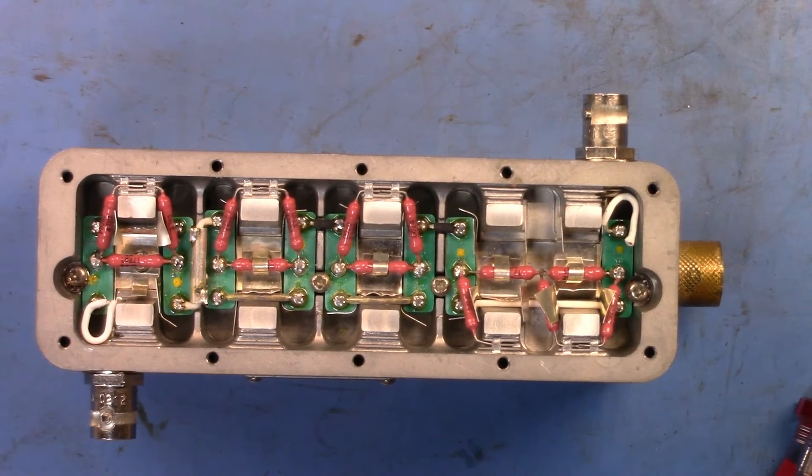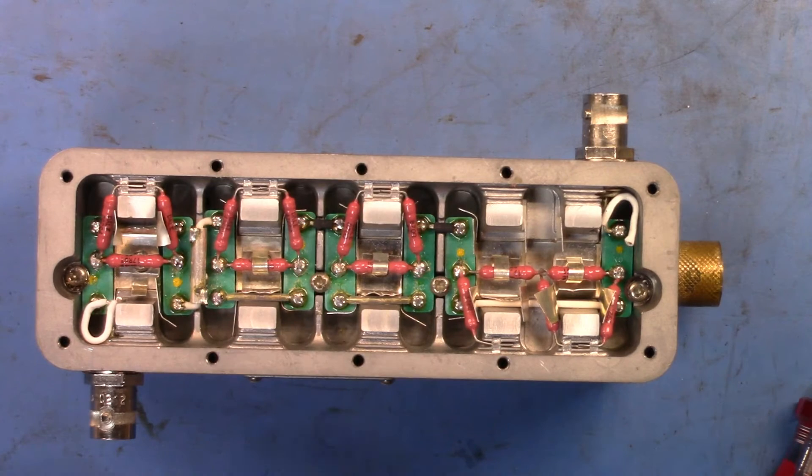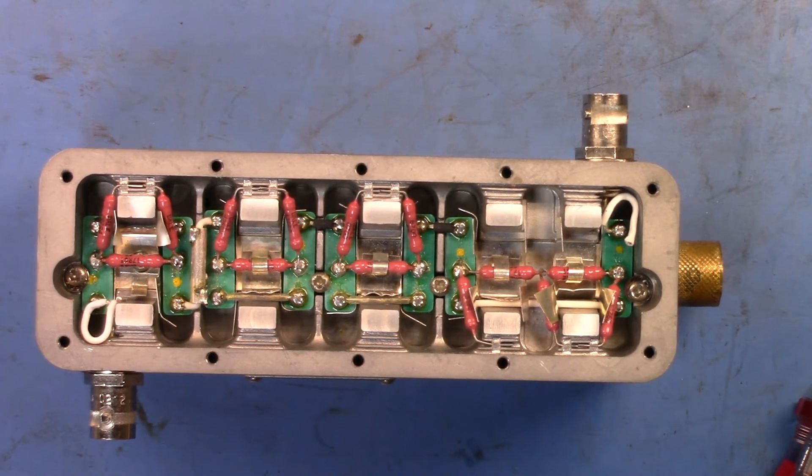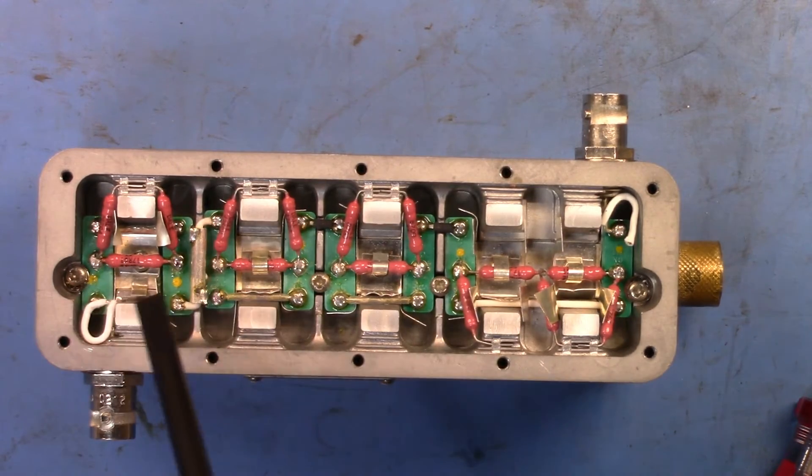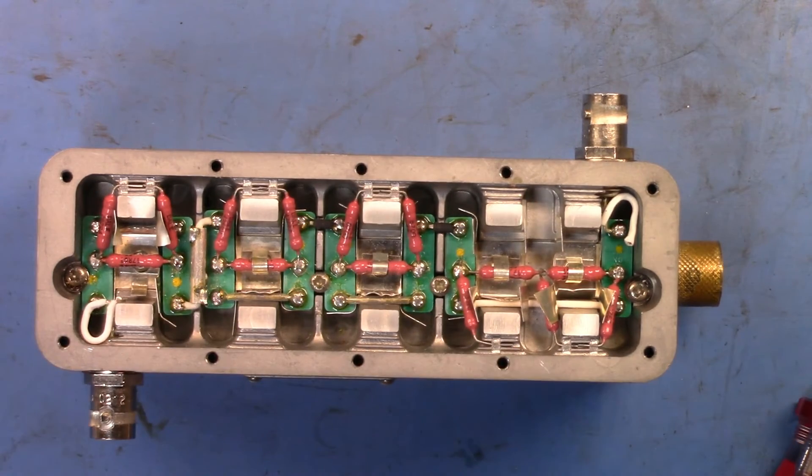Now the reason, and I mentioned this earlier, that there's no user serviceable components, is not just because these resistors are very special or something, but it's actually these little pieces of metal here. These things are actually bent at the factory to tune the attenuator to get it to be accurate.